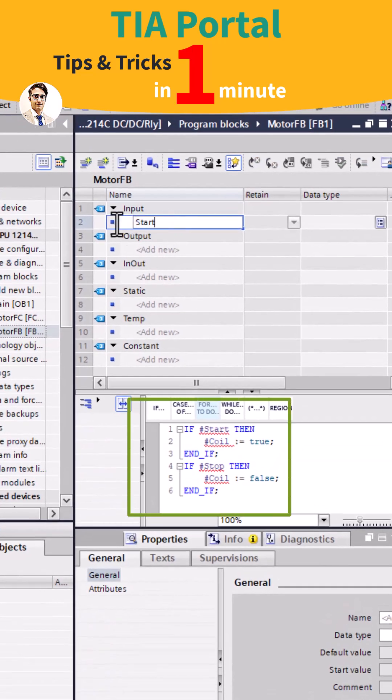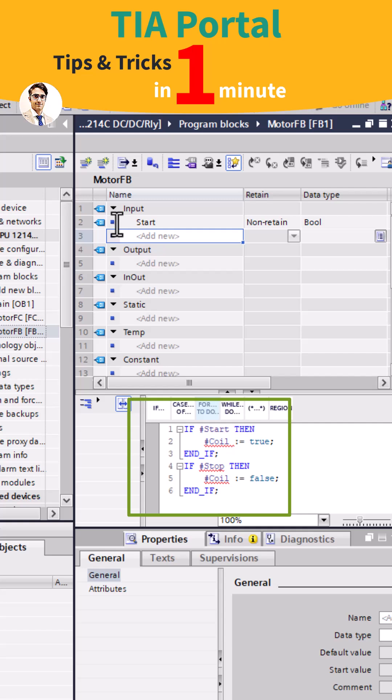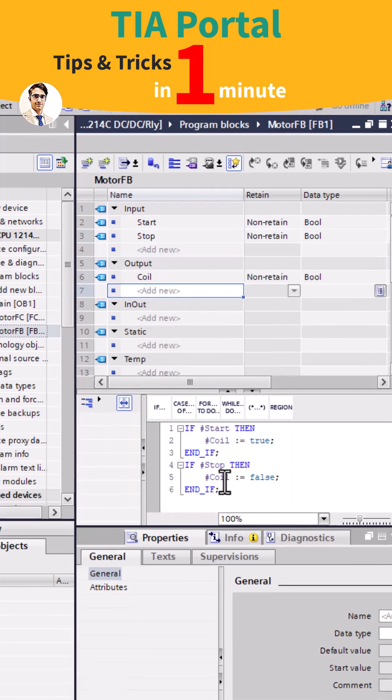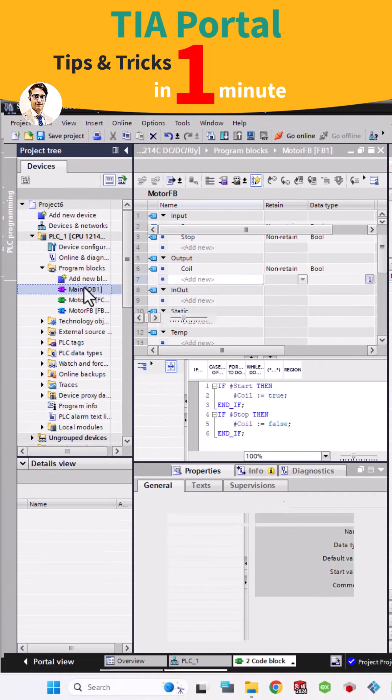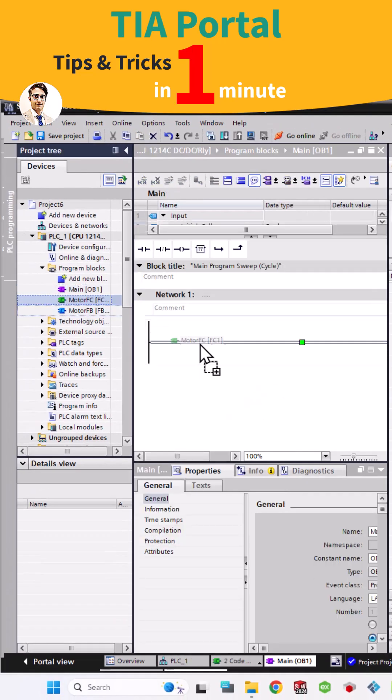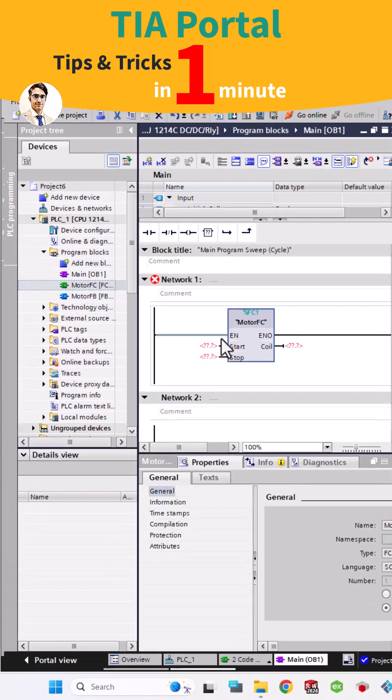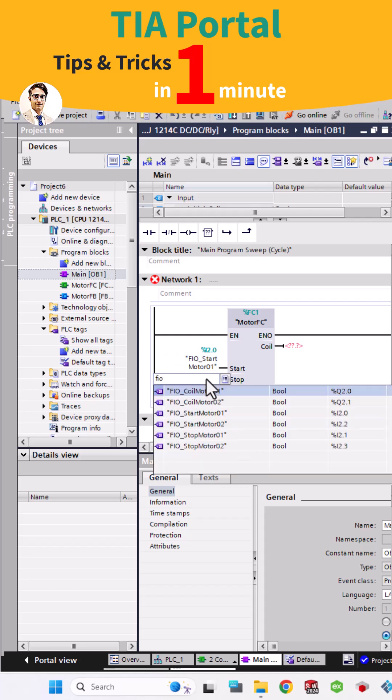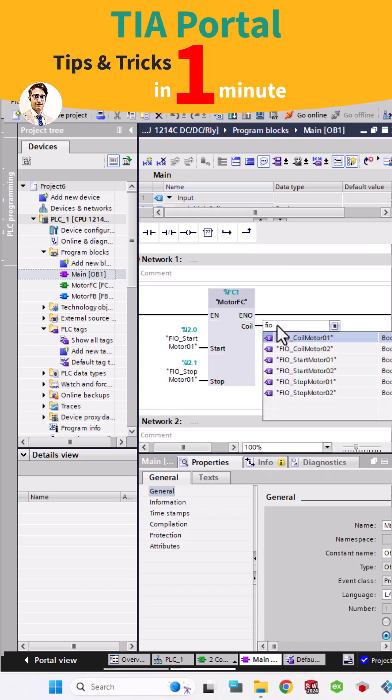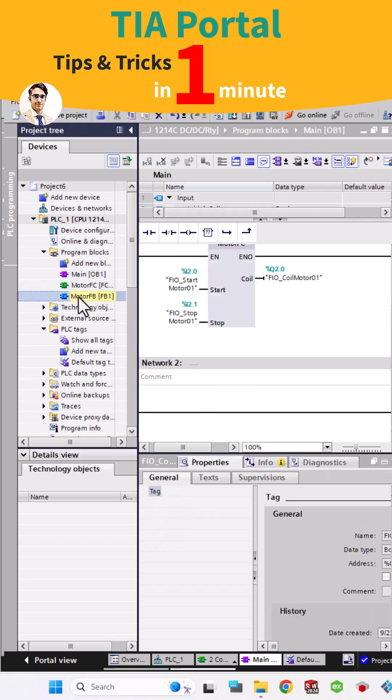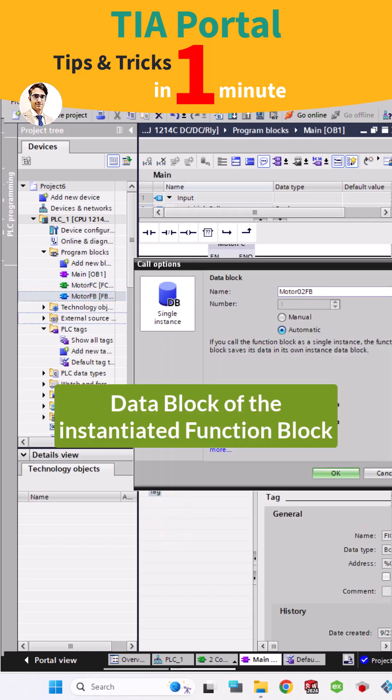I copy the code to create a function block, so the code for FC and FB are completely the same. As you know, when you instantiate the function block it automatically creates a data block, and each FB has its own data block.